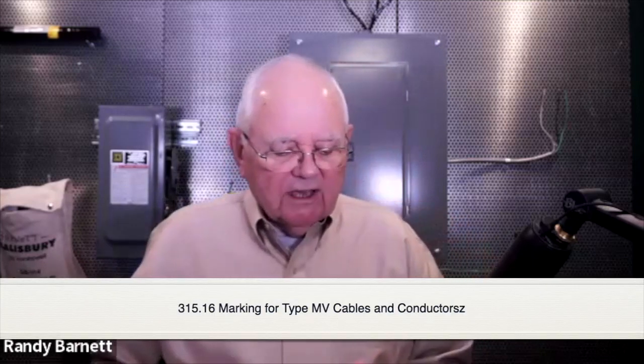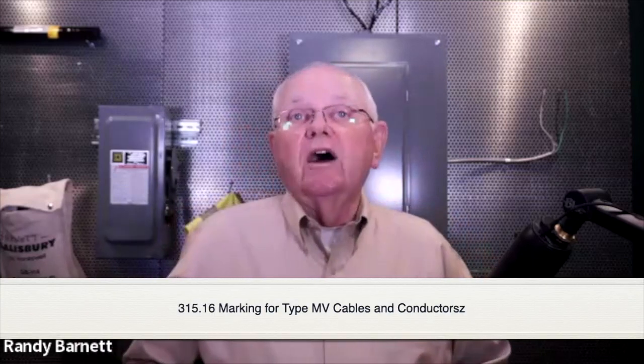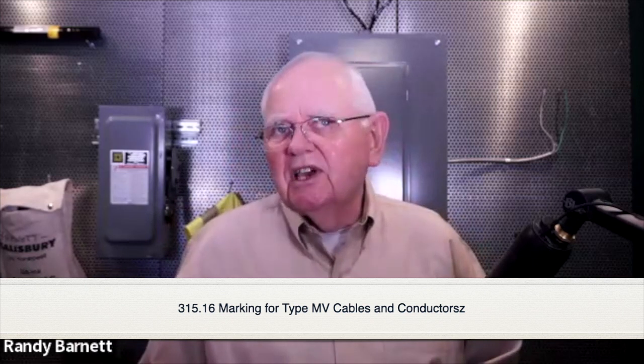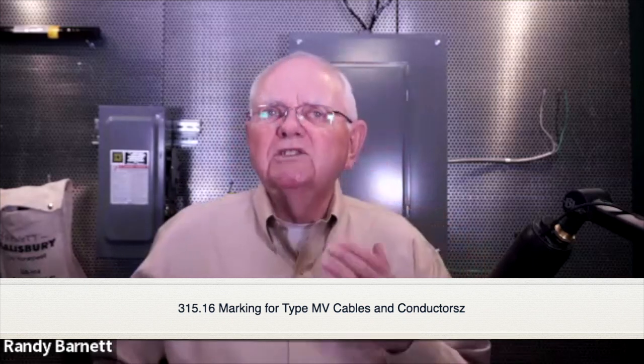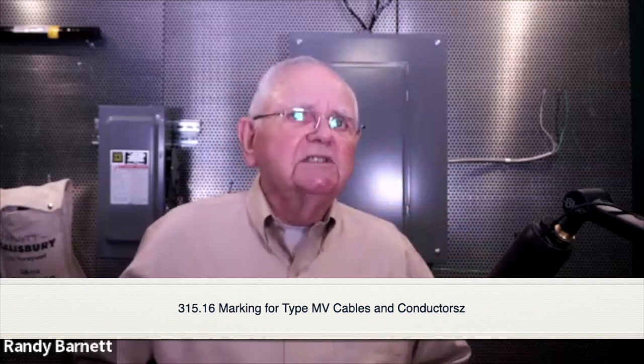First of all, it gives me the manufacturer's name and logo, which is fine. I call it power cable. And then it tells me UL. It also tells me CSA. So it's been tested by two nationally recognized testing labs, Underwriters Laboratories and the Canadian Standards Association, and found to meet the testing requirements. So if I install it properly in the field, according to the manufacturer's instructions and the National Electrical Code, this cable's good to use. So it's good to go, right?